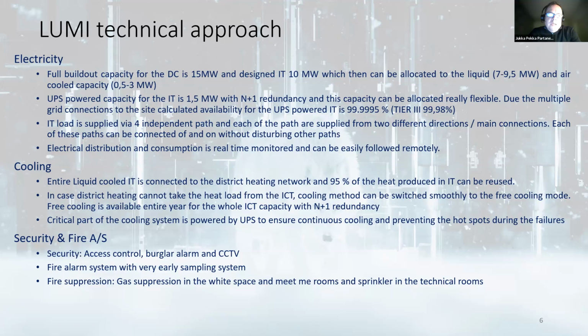Then cooling. The entire liquid cooled IT is connected to the district heating network, and 95% of the heat produced by the IT can be reused. In case district heating cannot take the heat load from the ICT, the cooling method can be switched smoothly to free cooling mode. And free cooling is available the entire year.